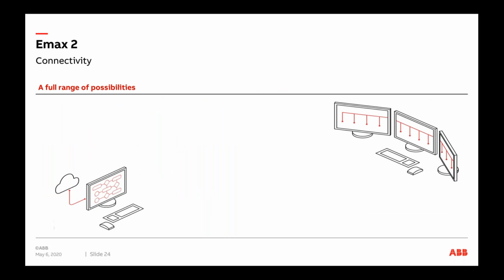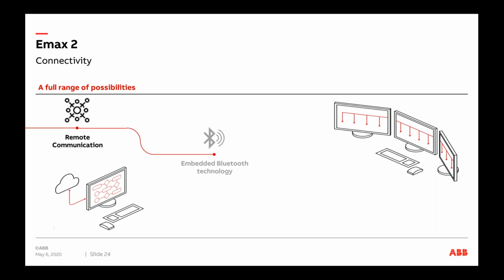So what possibilities do we get? Remote connection. Through our standard industrial universal communications like Profibus, DeviceNet, Ethernet, or Modbus RTU, we can communicate with the device with Emax 2. At a local level, we have embedded Bluetooth technology. So without having to open a panel door while the board is live, we can use a handheld mobile device or iPad to communicate with the breaker, to read the measurements, and also be able to change protection settings.